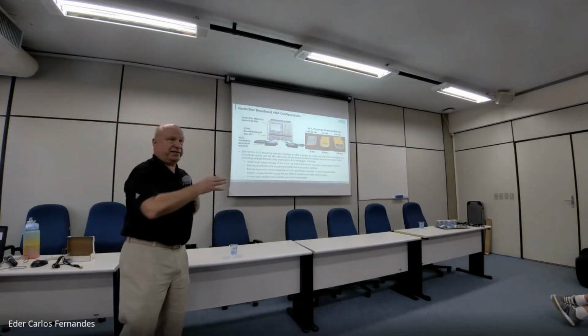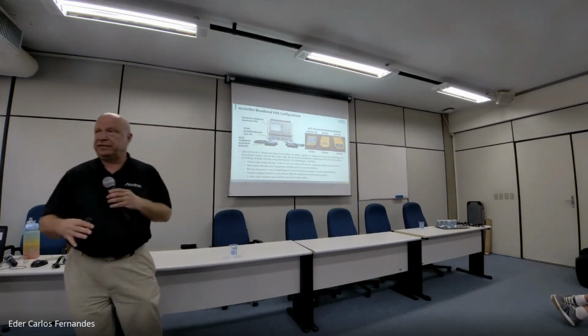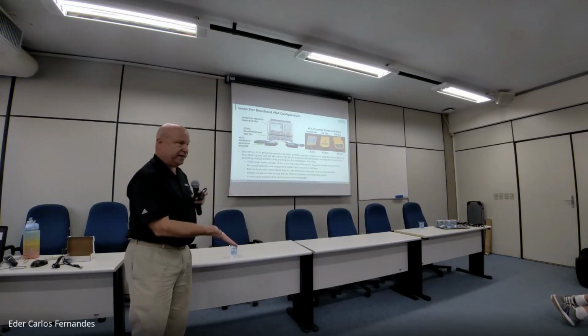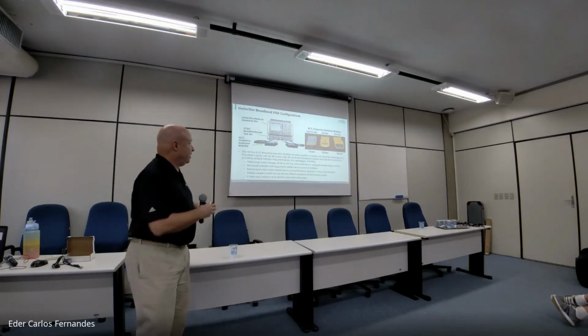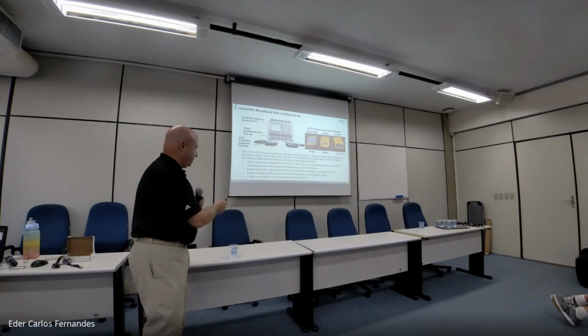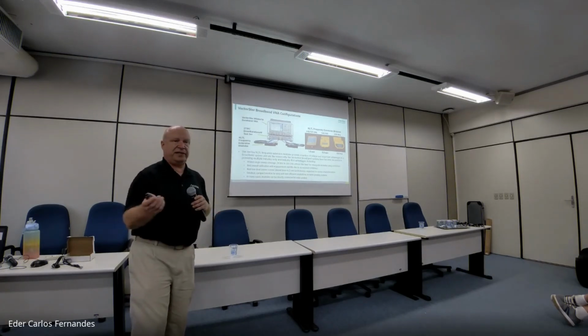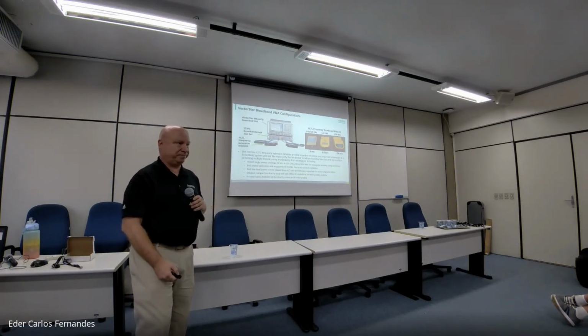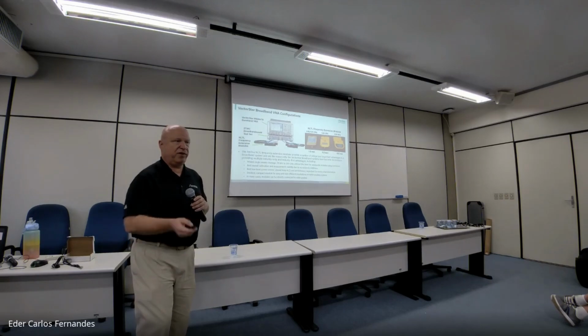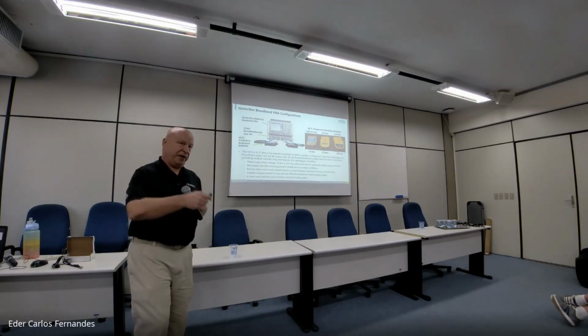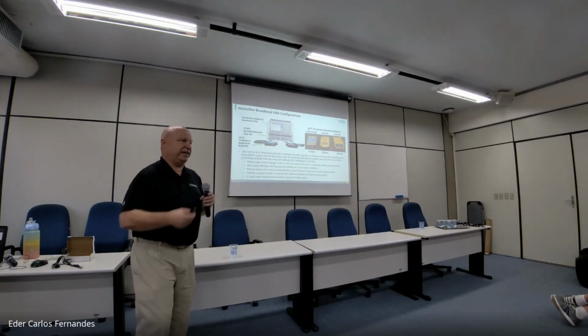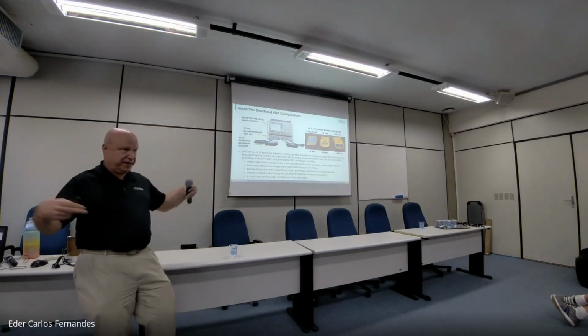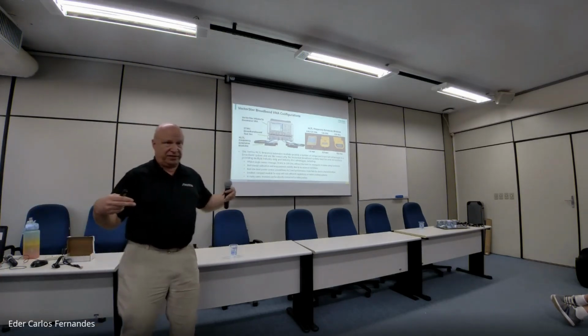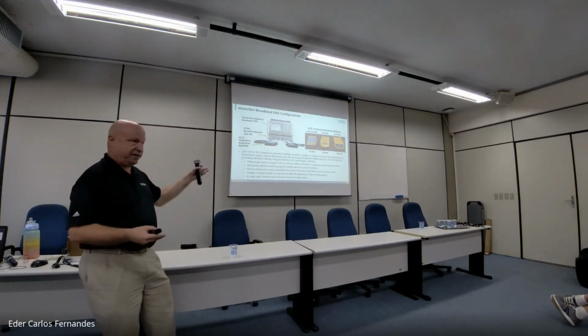So in most cases, given the size of these modules, they're basically the size of the palm of my hand. They fit right there. We can get the module to where we want to apply the signal, which in most cases is right at the wafer probe. So we avoid adding more cables. Remember how earlier we were talking about the distributed VNA, and I said you don't want those extra cables because those only add loss and create stability issues. Same thing is true here.